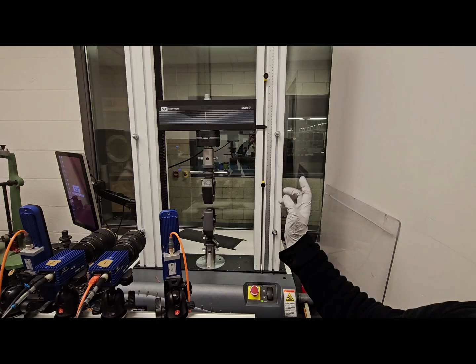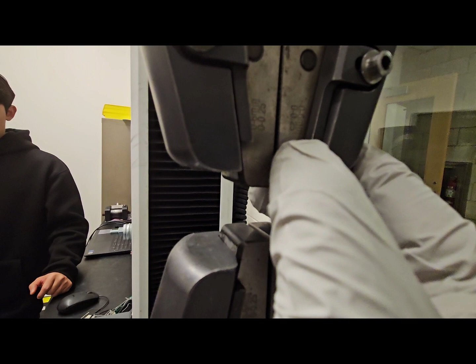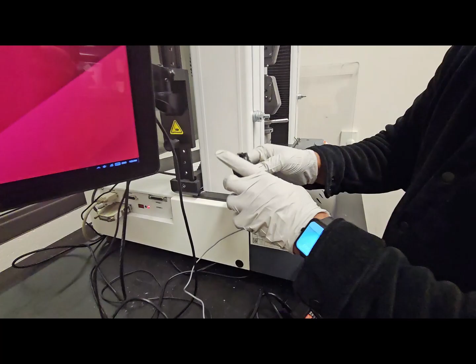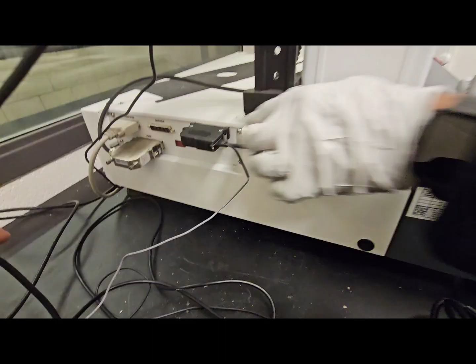Now we need to turn the Bluehill software on. For that we need to use the system over there. For the tensile block you need to use this clamp. Make sure you are using the proper clamp. If you see, this is written over here, 0 to 6 mm. That means your tensile sample has a thickness between 0 to 6 mm. We are using a tensile sample with a thickness of 5 mm for this clamp. We have some connections over here, and we need to use this extensometer.